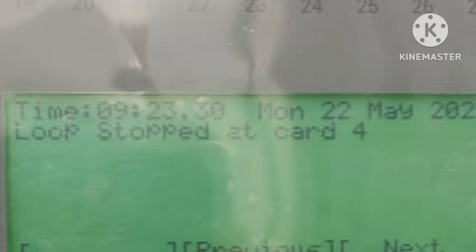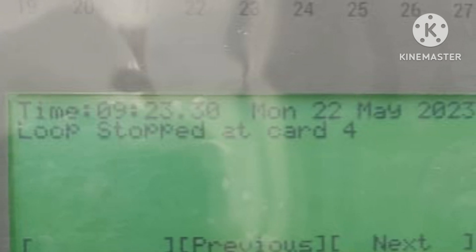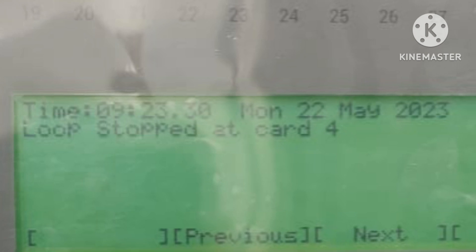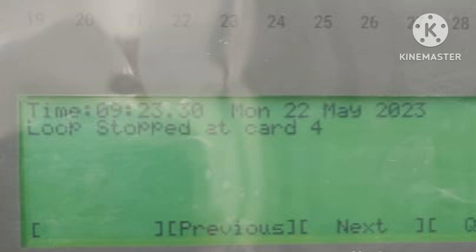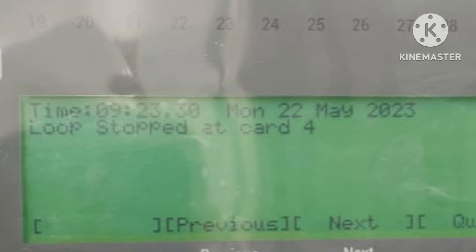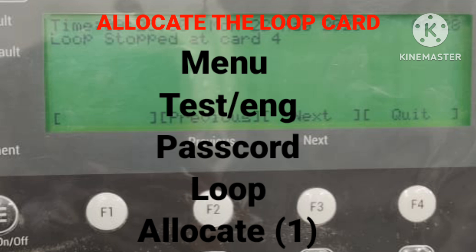First, relocate your card and try to allocate it. If it is not allocated, then troubleshoot for the short. To troubleshoot the short, first remove the return cable from the panel, then try to allocate. You will see in the allocations that after some particular device the allocation stops.